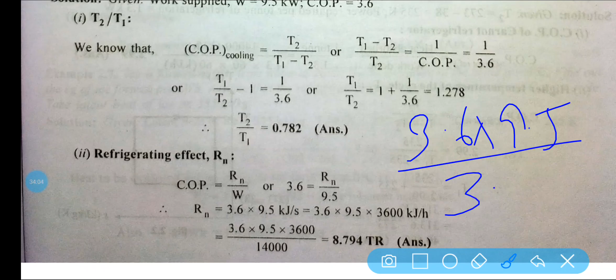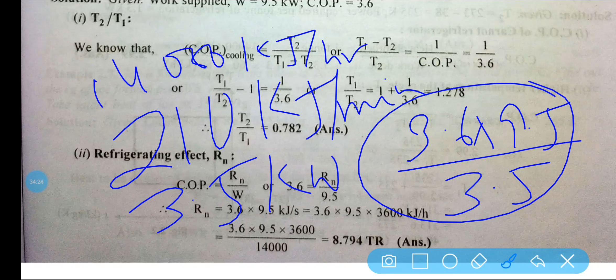Now if you divide it by 14,000 kilojoule per hour, since you know that is 1 ton of refrigeration, you will be getting 8.79 ton. Or if it is in kilowatt, you may write like this: 3.6 into 9.5 in kilowatt, divided by 3.5, you will be getting the answer in terms of ton. Because 1 ton is equal to 3.5 kilowatt, or 210 kilojoule per minute, or 14,000 kilojoule per hour. This is the meaning of 1 ton of refrigeration.